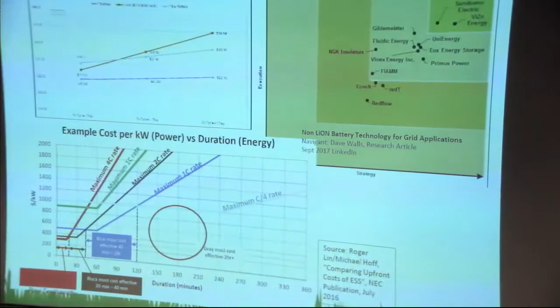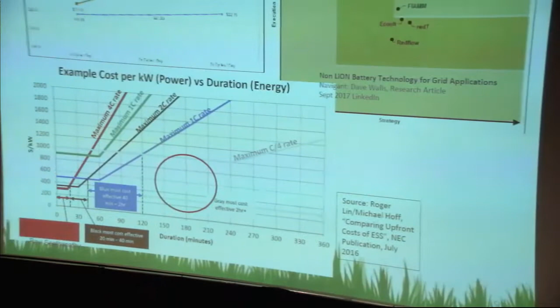If you come down to the specs part of it, it can lead you into wrong decision making if you're not careful - this was a discussion we had with electric companies and technology people the last 2 days. If I come down from long time on the right of the chart, say 360 minutes, the silver line looks like the lowest cost, because it's below the blue, red, black, and green lines. But as I come closer, asking for requirements in the 15-minute, 30-minute, 45-minute range, you suddenly find the silver is not the cheapest - it's actually the most expensive. The red line, which was the most expensive for long ranges, has now become the cheapest. So we need to be very careful what you specify, because what you specify is what gets tailored, and once you're stuck with it, that suit is yours.